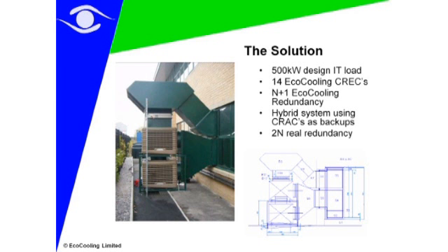One of the key issues with a ventilation system or a true free air system in Northern Europe is the air is actually too cold most of the time. So we have to heat it up. And we do that by creating a temperature loop which brings that hot air back into the cooler to warm the incoming air up. So we came out with a solution.